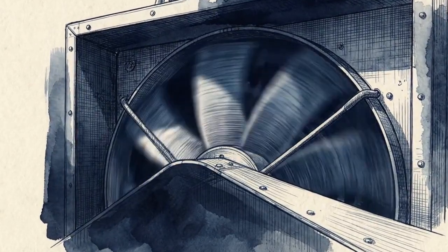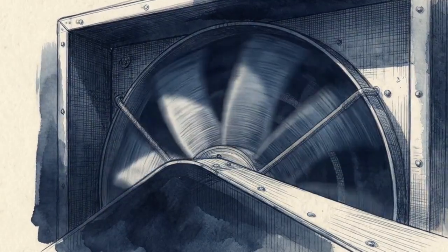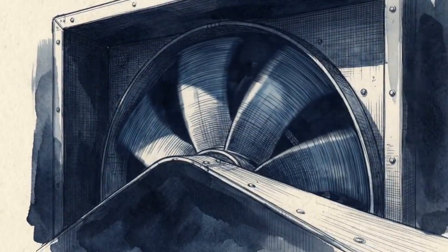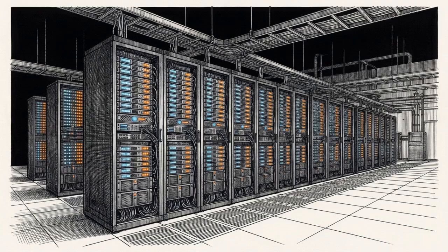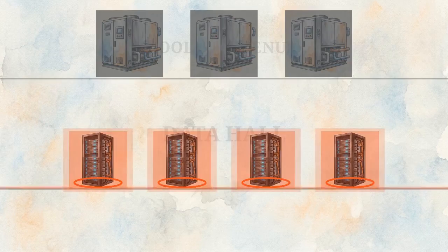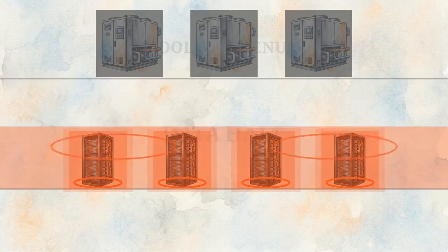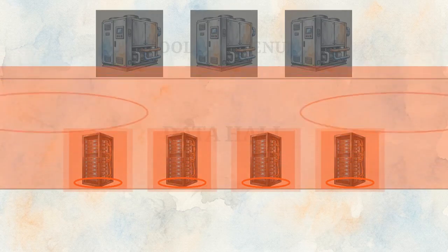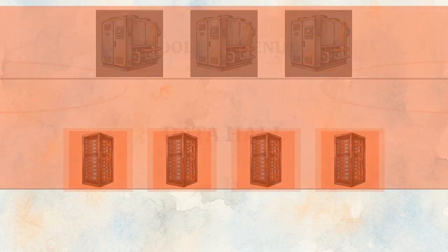The facility goes dark. The chiller compressors and condenser fans immediately lose power and halt. The IT equipment, however, is backed up by uninterruptible power supplies. The servers never power down, which means they instantly continue generating a lethal level of thermal energy into the data halls, even as the primary cooling systems sit idle.